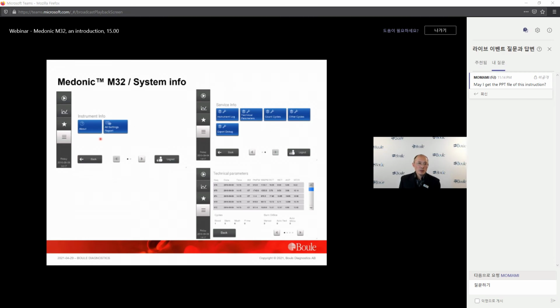The system info contains the serial number, the IP address of the instrument, and the technical parameters. There we can see very important parameters like the counting time for RBC and WBC, the aspiration time for whole blood, and the transfer time. These parameters actually reflect the correct aspiration and counting of either the dilution step or the measuring steps.